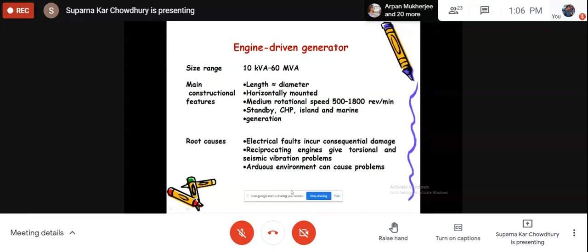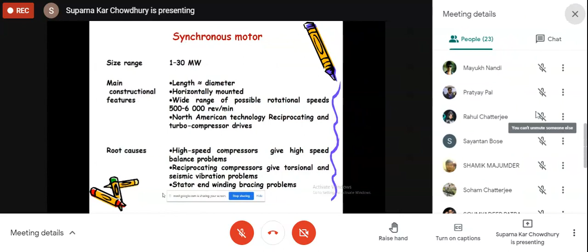Then synchronous motor. Now synchronous motor is widely used in the high power range, normally 1 to 30 megawatts. Here, length is almost equal to diameter, normally horizontal mounted, with a wide range of possible rotational speeds. Then root causes of failures: a high speed compressor gives high speed balance problem. Actually when it is a motor, it depends on what load it is driving. So if it is driving a high speed compressor, compressors have their own problem, balance problem, so that will affect the system. Reciprocating compressors have torsional and seismic vibration problems, so that will affect the machine. Stator end winding bracing problems are there when it is a high speed machine.